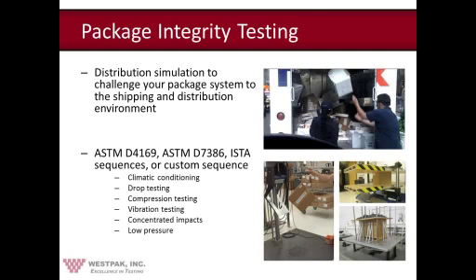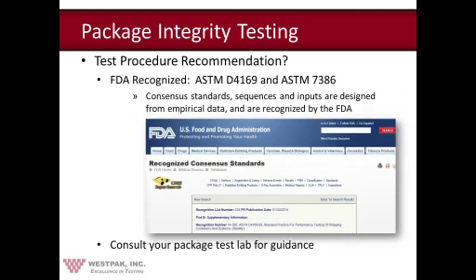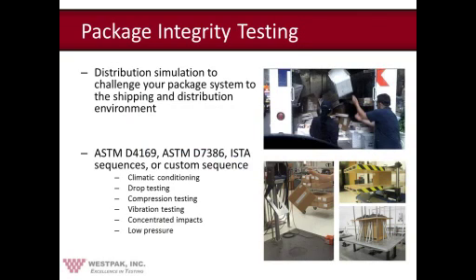Industry standards are usually referenced for this testing, and common procedures are ASTM D4169, ASTM D7386, different ISTA procedures such as 2A or 3A, or even a custom test sequence that your company may have come up with. These shipping simulations usually consist of climatic conditioning, drop testing, compression testing, vibration, concentrated impacts, and low pressure testing. And Herb, did you want to comment on this?